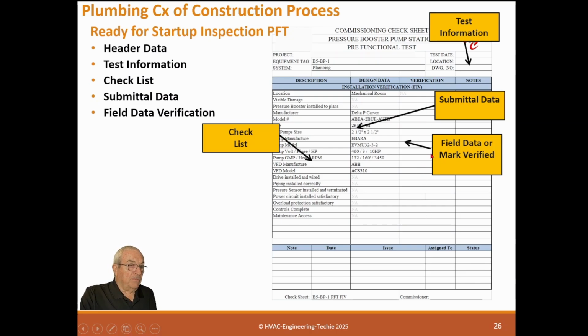And I always told the people, I don't want you putting a check mark, and I don't want you saying okay. I want you saying, I have verified this. Or if it's a test, like a startup test, you actually put the data in, the actual data. So if it's a 480 volt system, I don't want to write in 480 volt. I want to know what the voltage is on every leg of the unit. So I should have 3 readings that are all slightly different. And that means that someone's actually put a meter on and read them, and I want to see that. I want to see the current on each leg. And so that stuff is data that the operator actually needs.